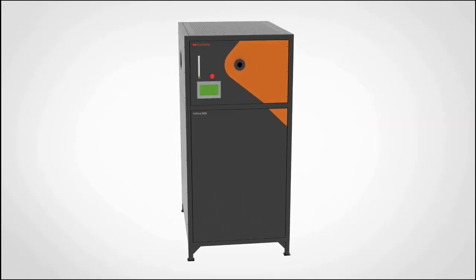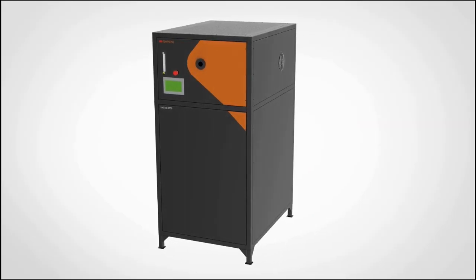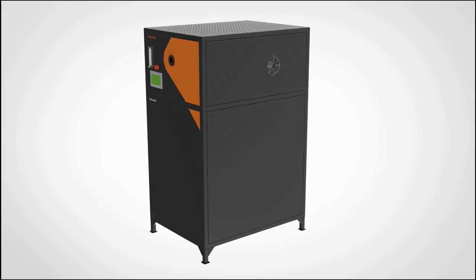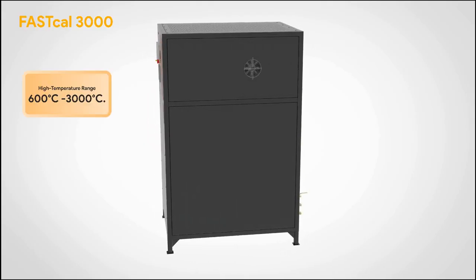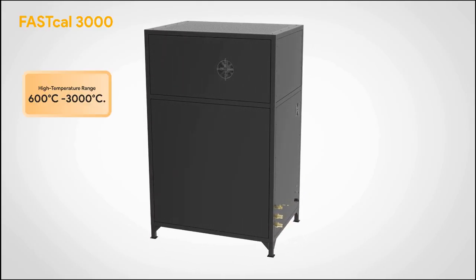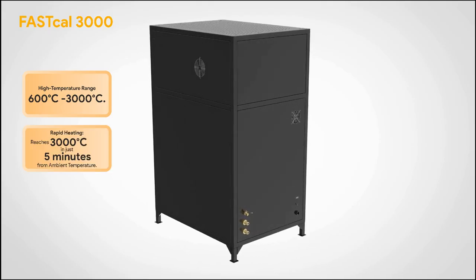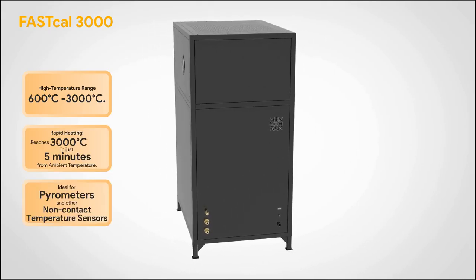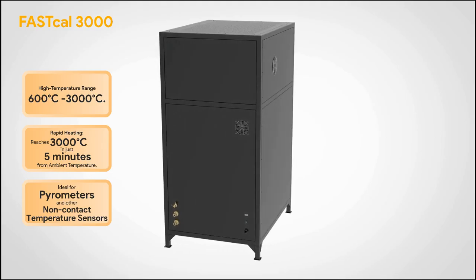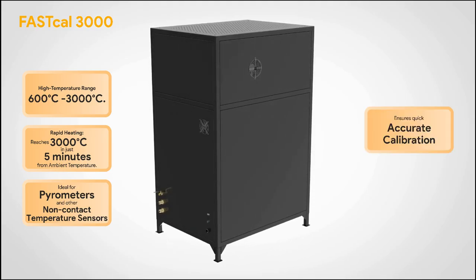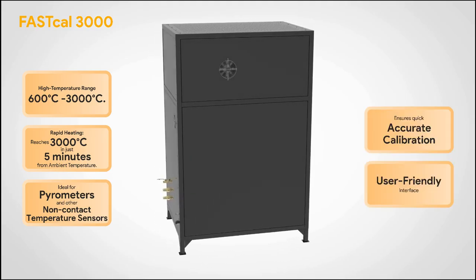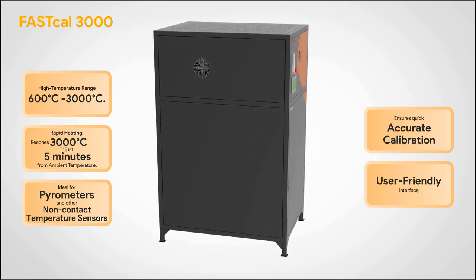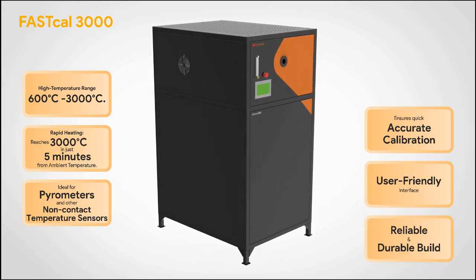This is FASTcal 3000, a high-temperature calibrator designed for quick and precise calibration of non-contact temperature sensors. It operates between 600 degrees Celsius to 3000 degrees Celsius and heats up to 3000 degrees Celsius from ambient temperature in just 5 minutes. With a durable build and user-friendly interface, it's ideal for precise temperature calibration.